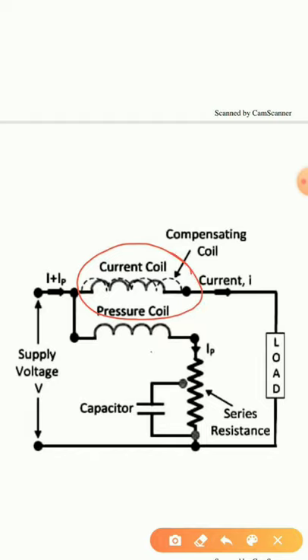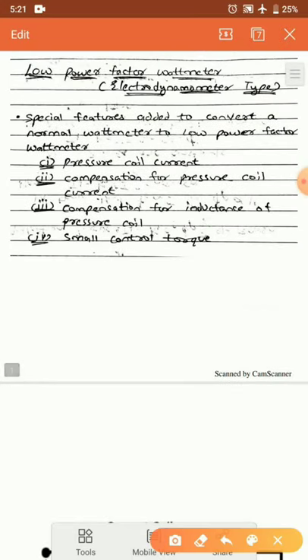To compensate for the extra current drawn by the pressure coil, a compensating coil is added in series with the current coil. Through mutual induction, this compensating coil also carries a current of Ip, but in opposition to the current coil. So if the current coil carries I + Ip and the compensating coil opposes with Ip, the net effect is that +Ip and −Ip cancel, and the current coil effectively shows only I. This is the second feature to be added.